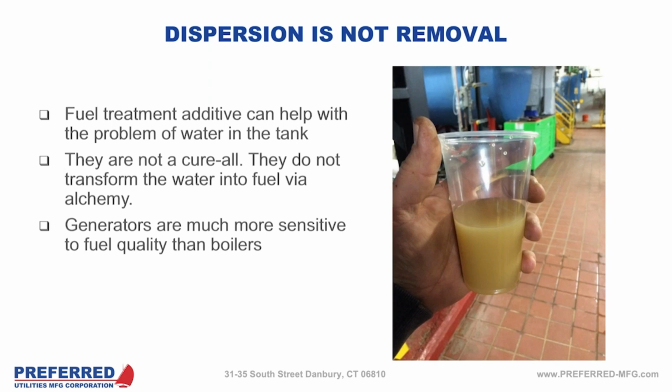But overall, a couple of things to look at if you are trying to fire burners and you're one of the burner guys out there: take a look in your sight glass in the back. If you see a lot of sparklers, which look just like little sparks firing from your furnace or from the main flame, that's water. That's water intrusion that you're seeing burning off. So that's a good indicator that you really need to do something with your fuel oil. Absolutely.